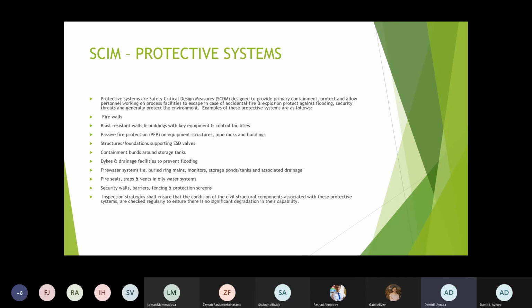So that was the equipment covered under this management system, and here you can see protective systems. Protective systems are safety critical design measures designed to provide primary containment, protect and allow personnel working on process facilities to escape in case of accidental fire and explosion, protect against flooding, security threats, and generally protect the environment. Examples are below: firewalls, blast resistant walls, and buildings with key equipment and control facilities, passive fire protection.